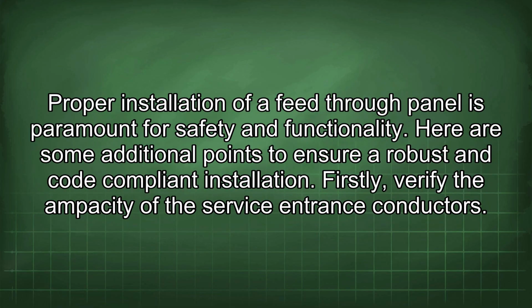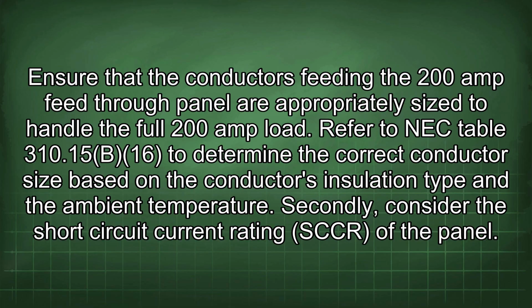Proper installation of a feed-through panel is paramount for safety and functionality. Here are some additional points to ensure a robust and code-compliant installation. Firstly, verify the ampacity of the service entrance conductors. Ensure that the conductors feeding the 200-amp feed-through panel are appropriately sized to handle the full 200-amp load. Refer to NEC Table 310.15(B)(16) to determine the correct conductor size based on the conductor's insulation type and the ambient temperature.